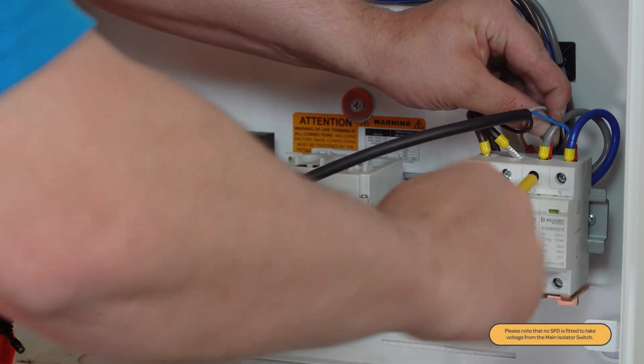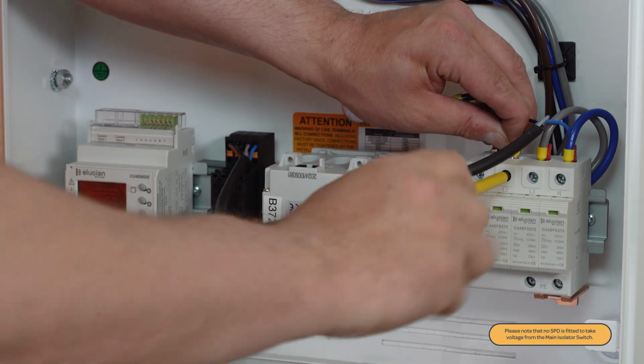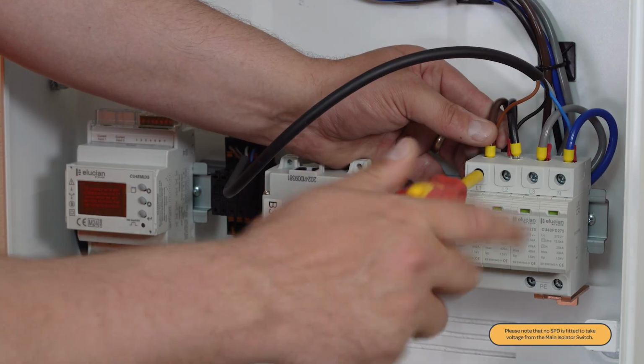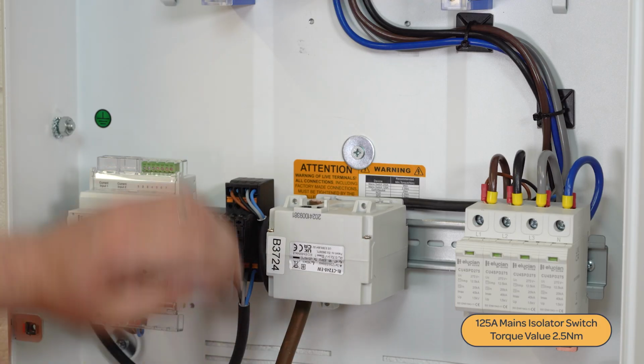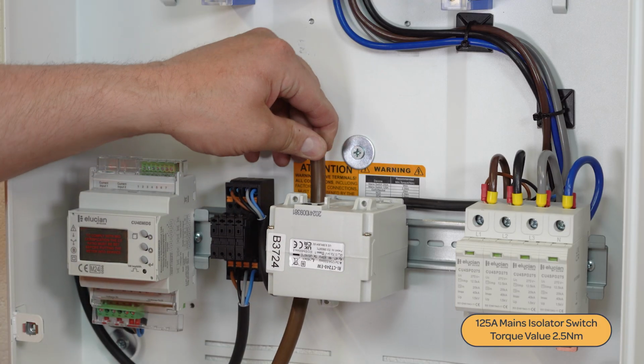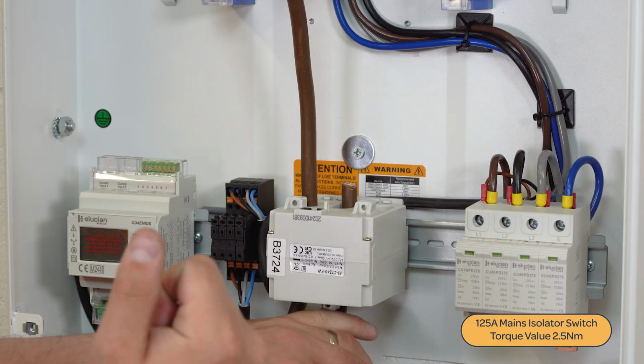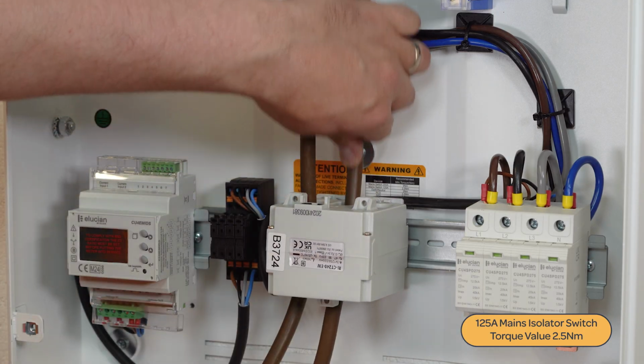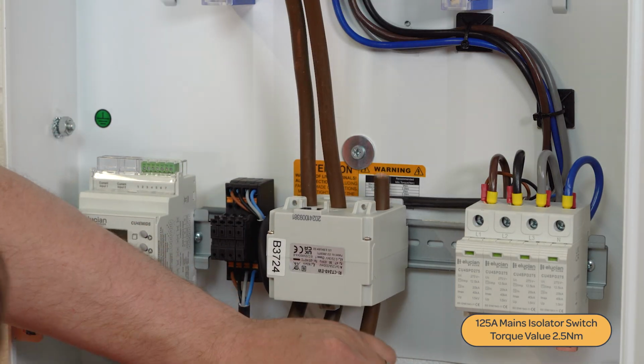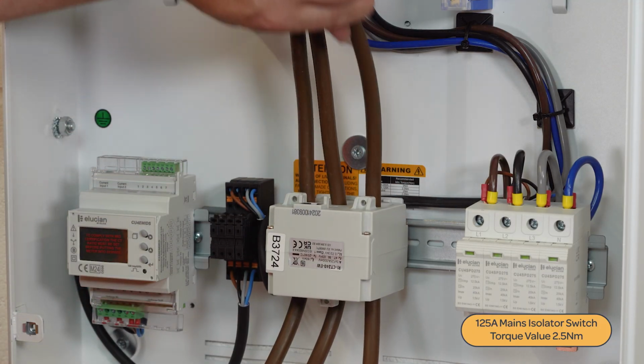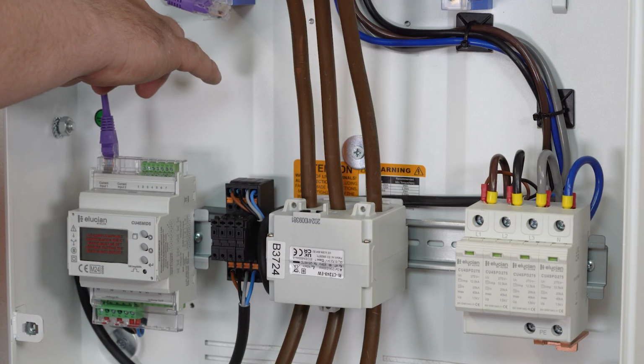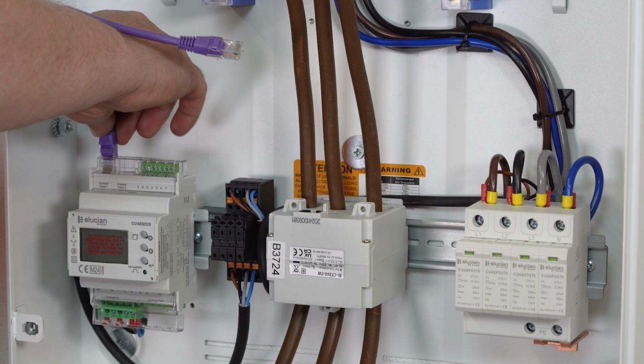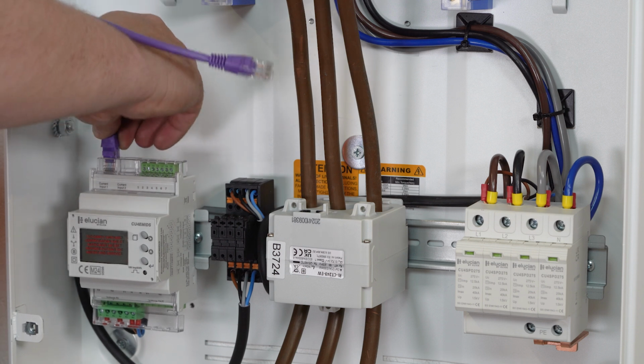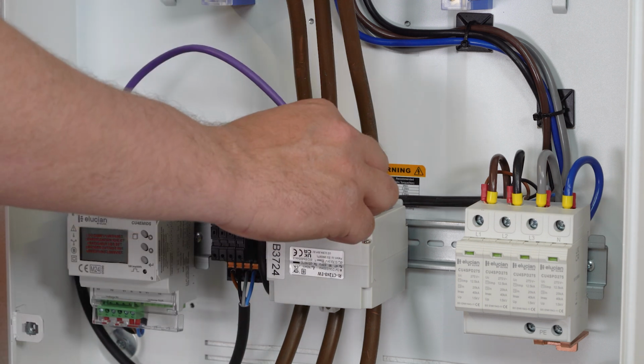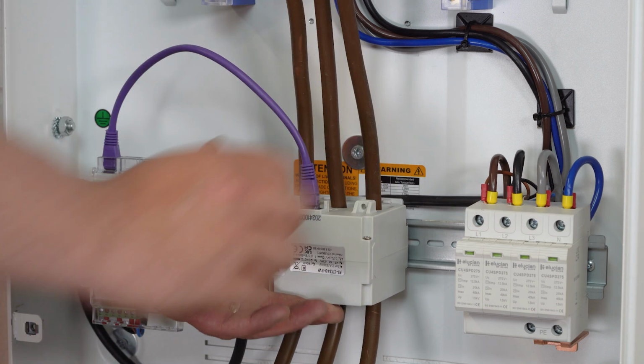The other end of the cables will need to be connected to the power. In this instance, we are not using the SPD. Bring the L1, L2 and L3 main supply conductors through the current transformer and terminate them on the underside of the main isolator switch and tighten with a torque screwdriver. Attach the RJ45 cable into current input 1 located on the top of the energy meter and attach the opposite end into the current transformer.